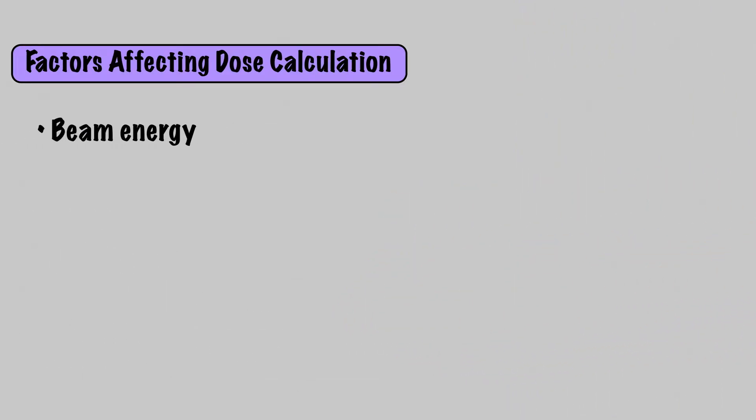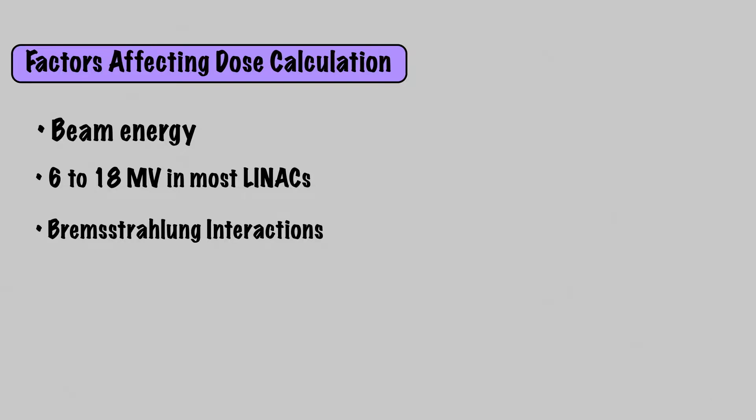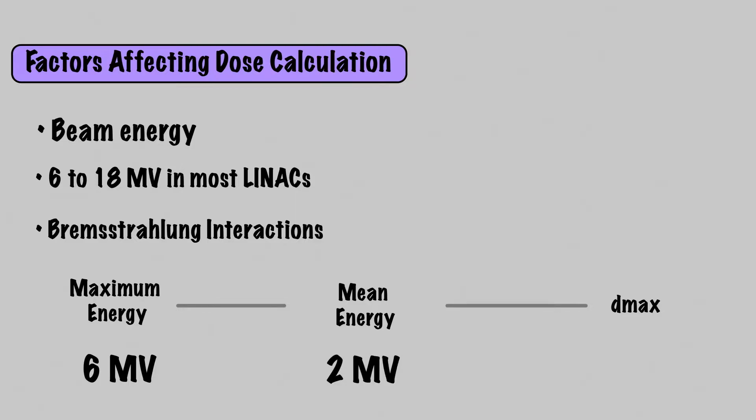The next factor to consider is beam energy, which can range from 6 to 18 megavoltage in most LINACs. Since generated photons are a result of Bremsstrahlung interactions, they have a spectrum of energies. Specific to each energy is a maximum energy, a mean energy, and a D-max. For example, a 6 megavoltage beam has a maximum energy of 6 MV and a mean energy of 2 MV, because mean energy is typically about one-third the max, and a D-max of 1.5 centimeters.